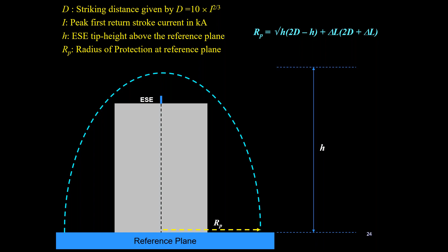Then what they do is consider that the height of the air terminal, if it has a physical height of 1 meter, they add that length advantage into the physical height, so that finally they calculate a volume of protection given by this equation, where RP is the radius of the volume at the reference plane.